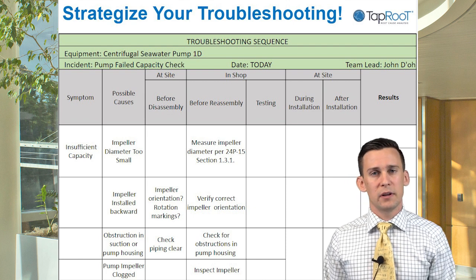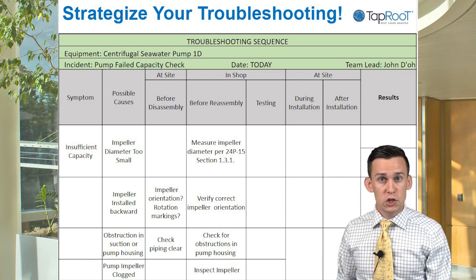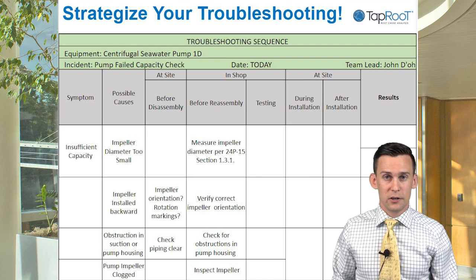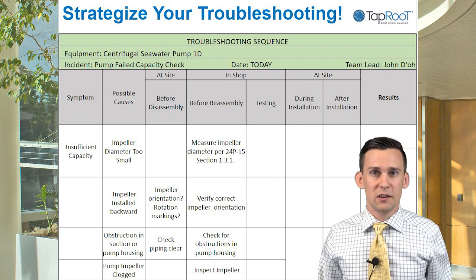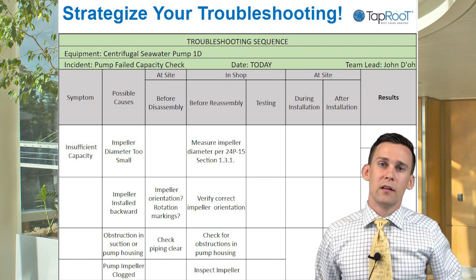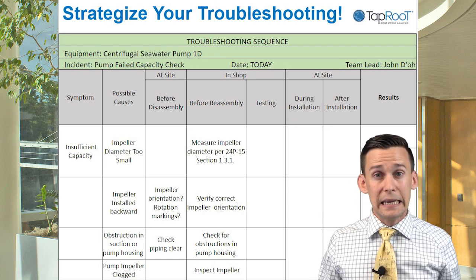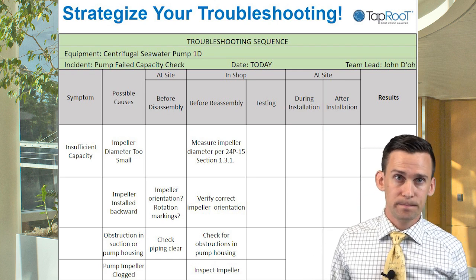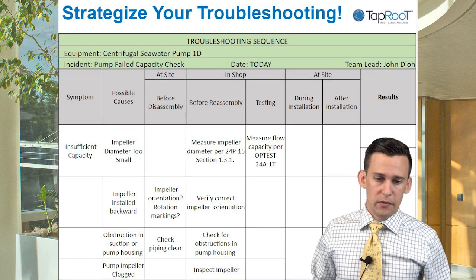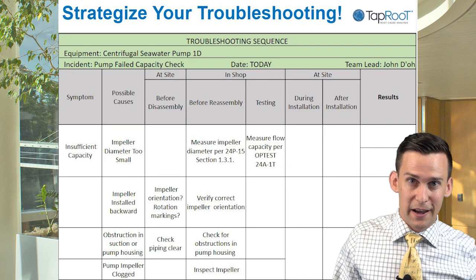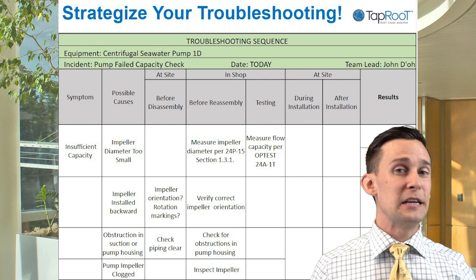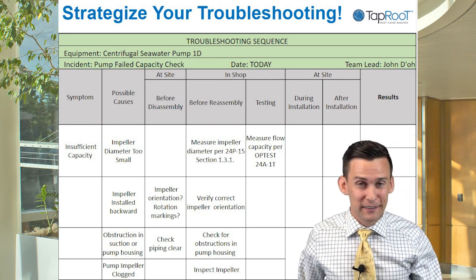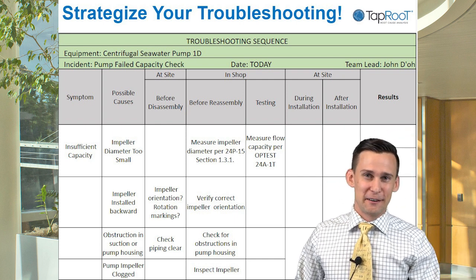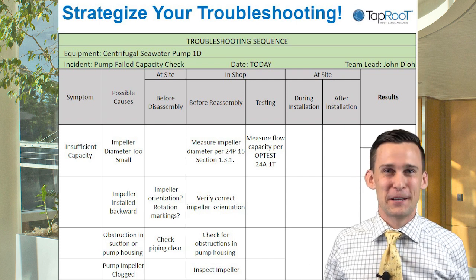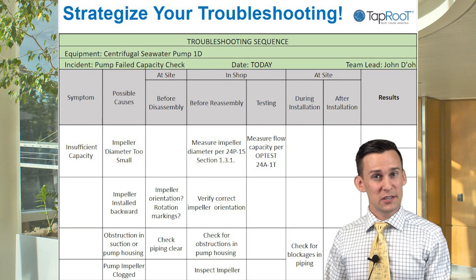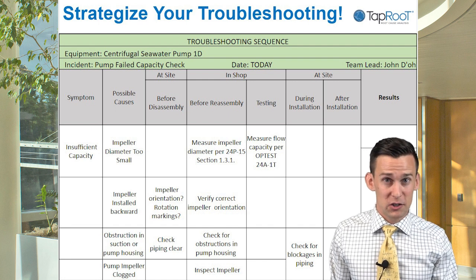This is where you'd be gathering things like: are there rotation markings on the impeller? Is there something etched in that says this side up, this side down, that may help indicate whether or not it was installed incorrectly? Then you want to go back and do your operational capacity tests after you put it back together, to make sure we didn't introduce any other errors. That's the most common reason machines fail—because we do maintenance on them. We want to make sure we don't introduce other errors. As we're reinstalling it, we want to make sure we're checking for blockages in the piping.